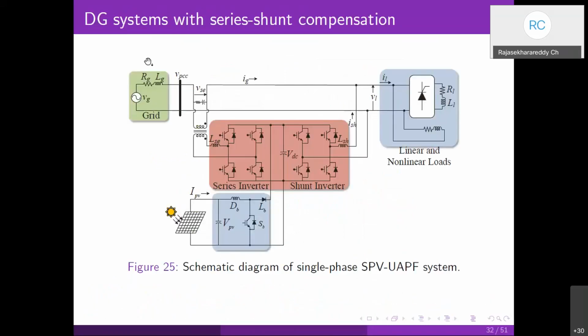So far we have looked at shunt compensation only, so those are the DG systems with shunt compensation capabilities. Now we will look into DG systems with series and shunt compensation capabilities. In the previous case, during low voltage ride through, the shunt voltage source inverter could only provide reactive current, but it does not show any effect on load voltage. But if you take a series voltage source inverter in a series shunt configuration like this, then during a low voltage condition we can also maintain the load voltage constant and sinusoidal.